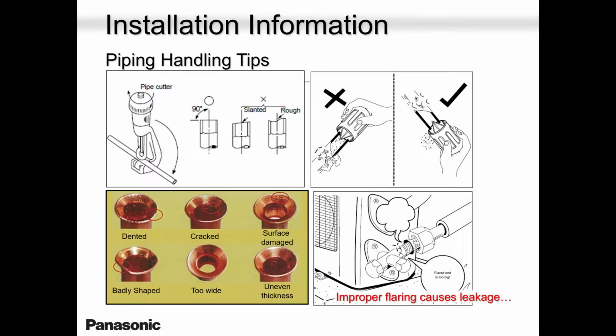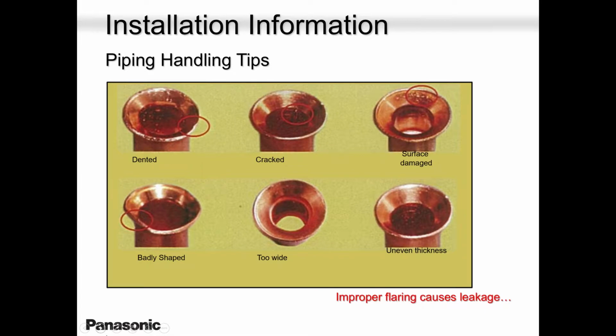These are simple practices. I'm just reminding you guys. I know most of you guys are doing this for years and years, 30, 20, 15, 5 years. But please, these are minor things that can cause major problems if you don't do them. So always remember to deburr after you cut your pipe. Apply a little bit of oil before you flare. That's the best thing you can do to avoid cracks, you know.